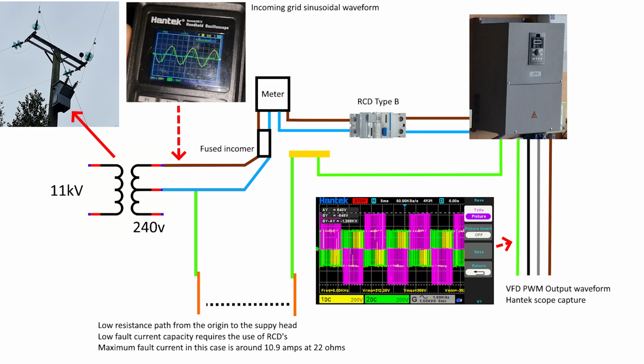The neutral conductor is also then referenced to earth via an earthing electrode located on the transmission pole. This is supposed to make a low resistance connection to the ones located around the building, but your results may vary on a lot of factors, which is why modern standards have since switched to a direct bond at your main incoming fuse, like a TNCS or other electrical installation system. The devices used to create 3-phase will need a good earth connection, or else you will get undesirable results such as voltage and frequency instability.